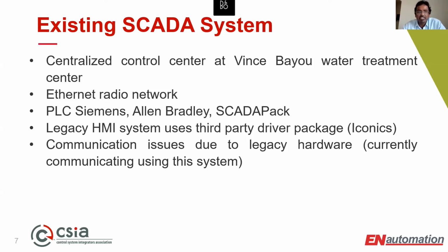The legacy system relied on a third-party driver package in order to communicate with these PLCs. And normally with third-party drivers, you have to have one driver suite for each platform or each model of PLC. So you would have to have a Siemens driver suite, an Allen Bradley one, a SCADApack one. But VT SCADA's inbuilt drivers made sure that we didn't have to rely on any other driver software for communication.